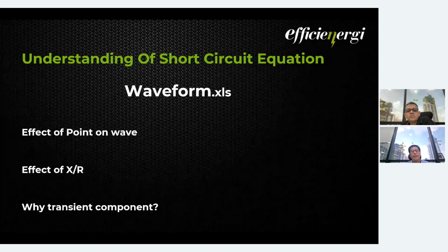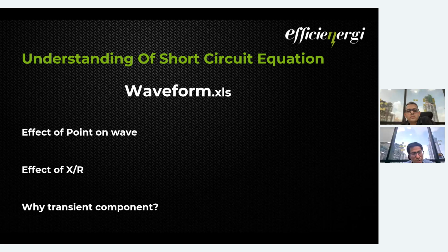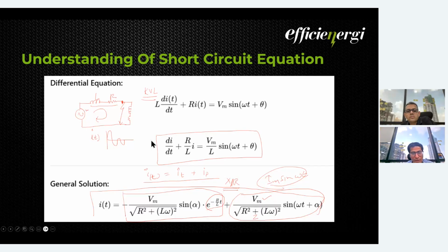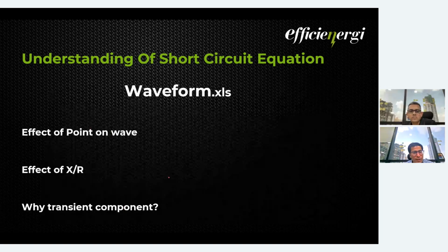But in reality, the fault is not always happening on the zero crossover of the voltage. Fault can occur at any point on a wave. So we are going to see the effect of the point on the wave, and on which factor it really has an effect, whether it is a transient factor or a steady state factor. Then we will see what is the effect of X by R.